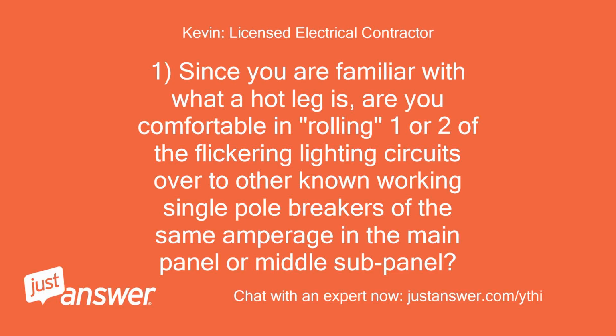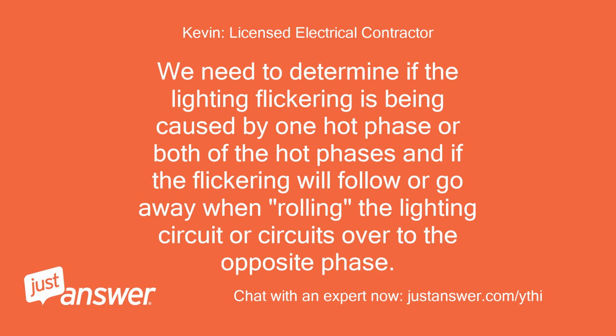1. Since you are familiar with what a hot leg is, are you comfortable rolling one or two of the flickering lighting circuits over to other known working single-pole breakers of the same amperage in the main panel or middle sub-panel? We need to determine if the lighting flickering is being caused by one hot phase or both of the hot phases, and if the flickering will follow or go away when rolling the lighting circuit or circuits over to the opposite phase.